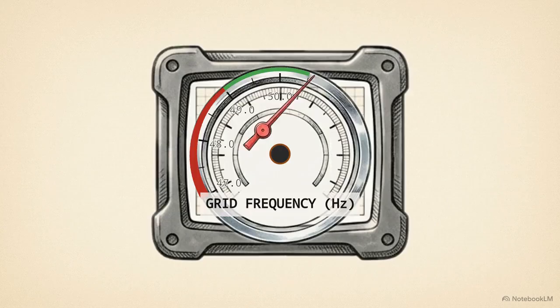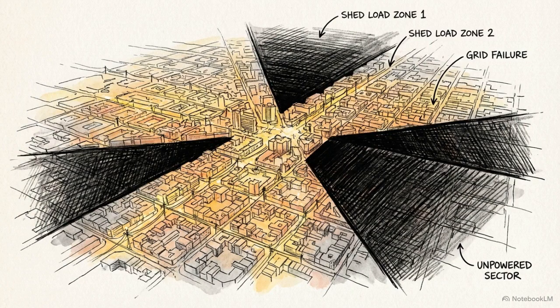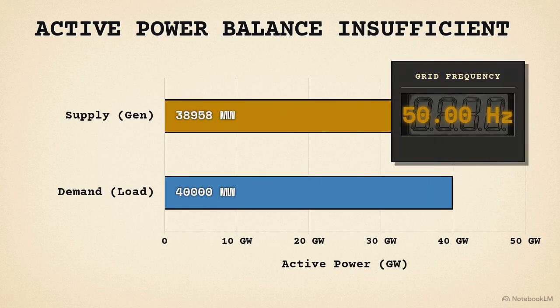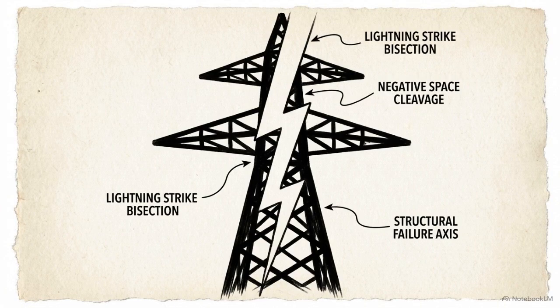The sudden loss of massive generation caused the grid's frequency to plummet. This triggered the automatic low-frequency demand disconnection, or LFDD, a defense plan that sheds load to balance supply and demand. The LFDD failed to save the grid because it is designed exclusively to fix active power imbalances. It is entirely powerless to correct a grid that has structurally lost AC synchronism.